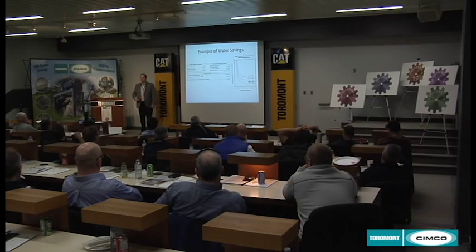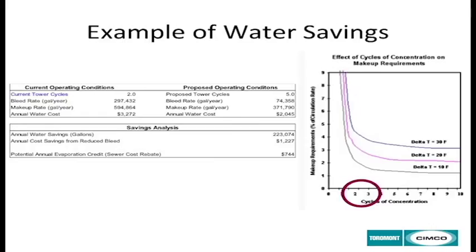Some facilities in the Guelph, Brantford, Cambridge area, you can't cycle up too much unless you use soft water. But if you're in many other cities that have lake water, where the typical conductivity or TDS of your water is around 300, you could operate 5 cycles of concentration. Anything higher than 5 or 6 or 7 cycles of concentration, you're not getting the savings. There's no additional savings. You're just accumulating more dirt in your system. But if you're running 2 or 3 cycles and you want to change it to 5, there's lots of savings to be made. Okay?